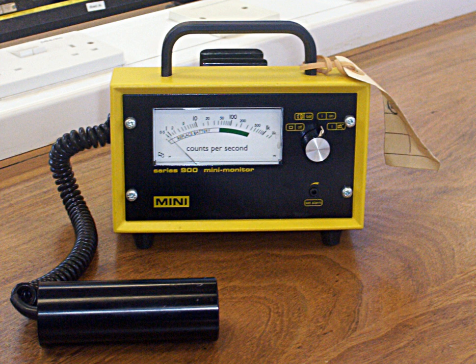The window is usually made of mica with a density of about 1.5 to 2.0 mg per square centimeter. Alpha particles have the shortest range, and to detect these the window should ideally be within 10 mm of the radiation source due to alpha particle attenuation. However, the Geiger-Müller tube produces a pulse output of the same magnitude for all detected radiation, so a Geiger counter with an end-window tube cannot distinguish between alpha and beta particles.